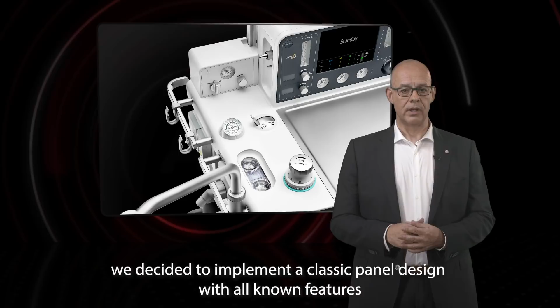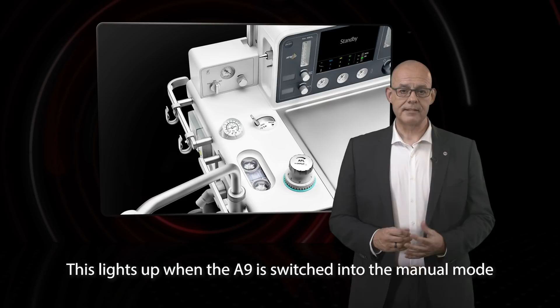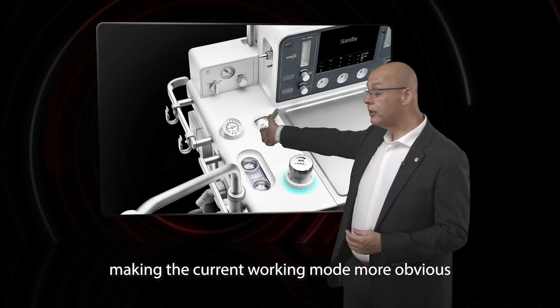To ensure a good look and feel, we decided to implement a classic panel design with all known features such as check valves, the APL valve, auto manual switch, the manual breathing bag and a classic pressure gauge. A nice feature that draws attention is the illumination around the APL valve. This lights up when the A9 is switched into the manual mode, making the current working mode more obvious.